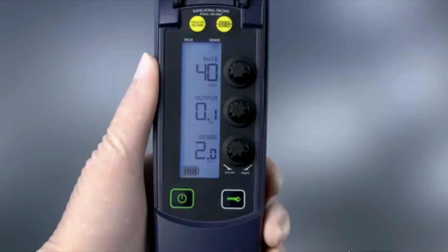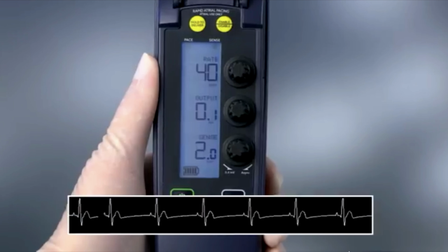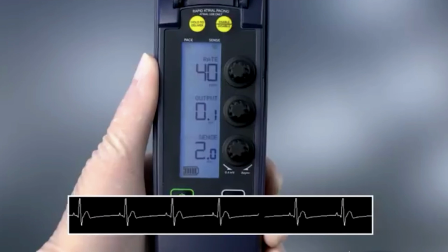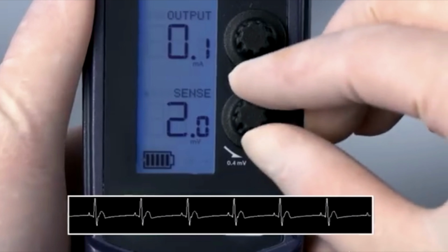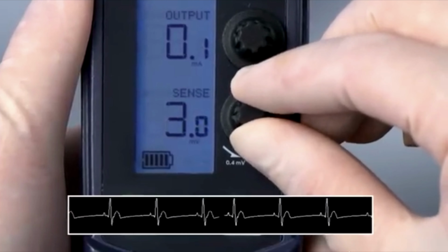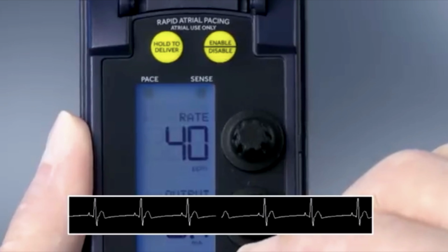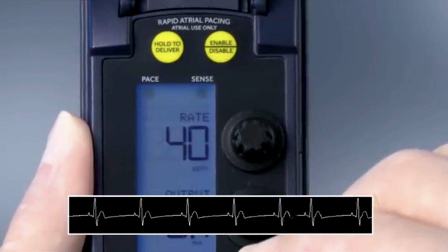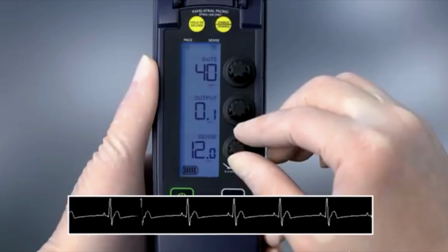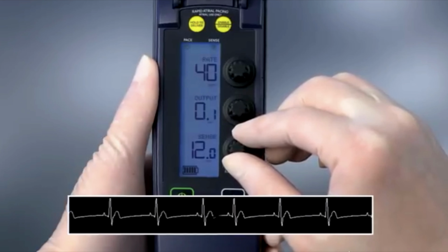In other words, the R wave is at least 2 millivolts. Monitor the patient's ECG to ensure the sense indicator matches the device lights. Slowly turn the sensitivity dial clockwise, which increases the millivolt value, until the sense indicator stops flashing. The pace indicator flashes continuously, but capture is not likely because the output value is set to the minimum.